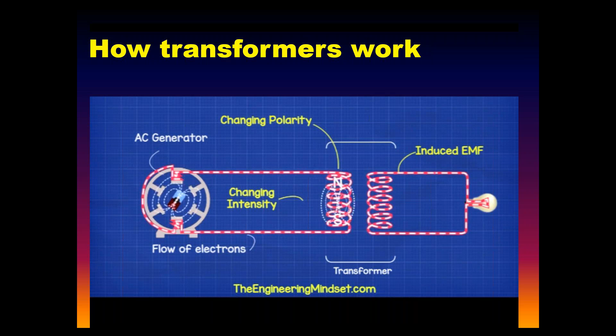down voltages and currents. In your operating rooms or cabinets, we still have isolated power. If you still have environments that have isolated power, the turns are the same, so we can put in 120 volts in, we get 120 out. Isolation comes in in that now the neutral on the secondary is no longer a reference to physical ground. We'll see some of the significance of that again as well.